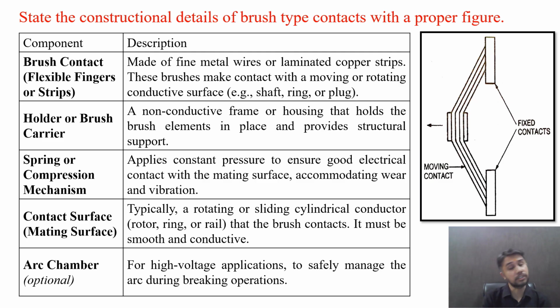Holder or brush carrier: a non-conductive frame or housing that holds the brush element in place and provides structural support. Spring or compression mechanism: the spring applies constant pressure to ensure good electrical contact with the mating surface, that is the rotating part, accommodating wear and vibration. The contact surface is typically a rotating or sliding cylindrical conductor, that is the rotor, armature itself, ring or rail type of contact that the brush contacts. The contact surface is circular inside, and the brush connects to the outer periphery of that rotating part. It must be smooth and conductive.